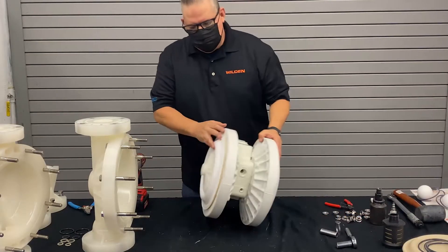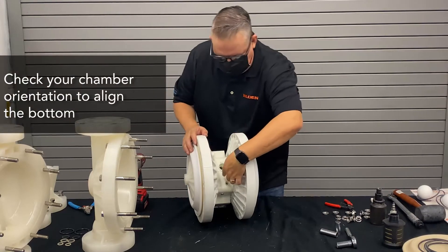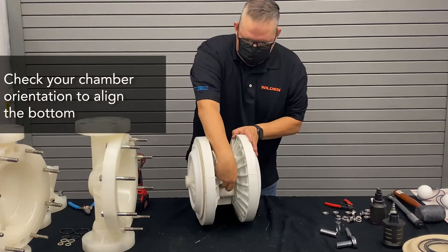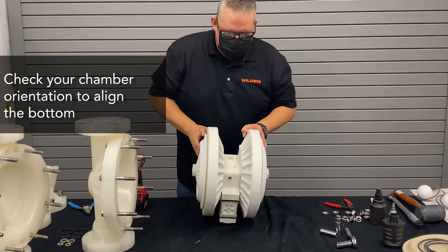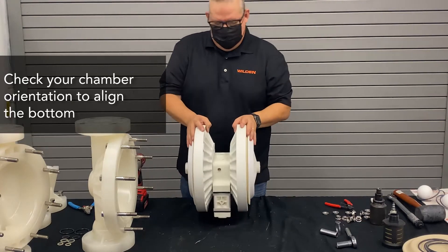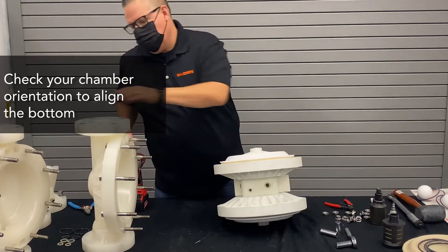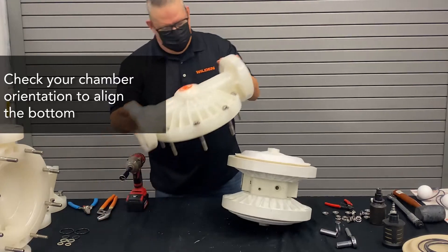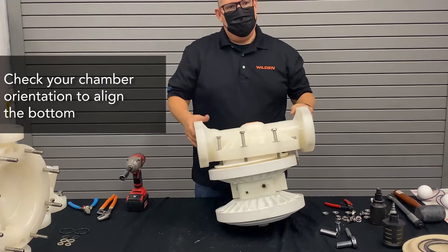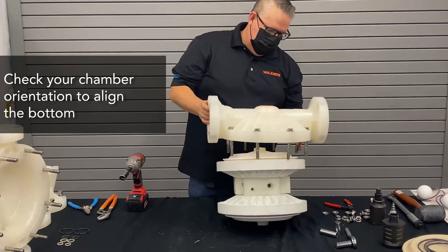Now that we have our diaphragms installed, we want to look at the orientation. This says Pro-Flo Shift — this is the bottom. You'll notice on the plastic, opposite to the metal pumps, the plug is on the bottom. When you go to put the chamber on, you always want to orient the chamber so the bottom faces the bottom. The bottom is always going to be the bell where the ball sits, so it's easier to tell.